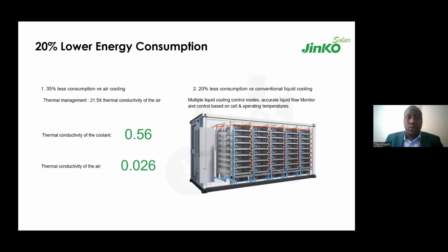And because of the liquid cooling mechanism, there is reduced energy consumption, as there is no need for high power cooling or HVAC units. And of course we have very good thermal conductivity for the cooling agent we're using, a mixture of water and coolant, compared to the thermal conductivity of air, which is about 21.5 times higher.